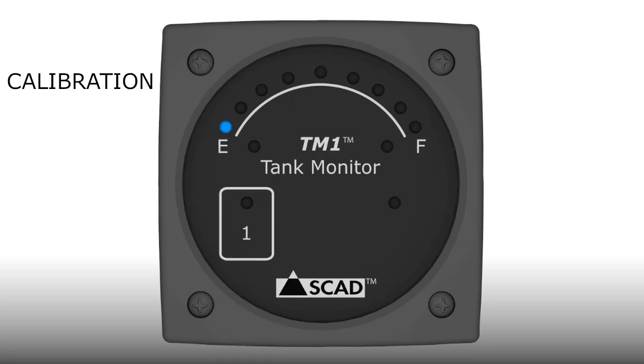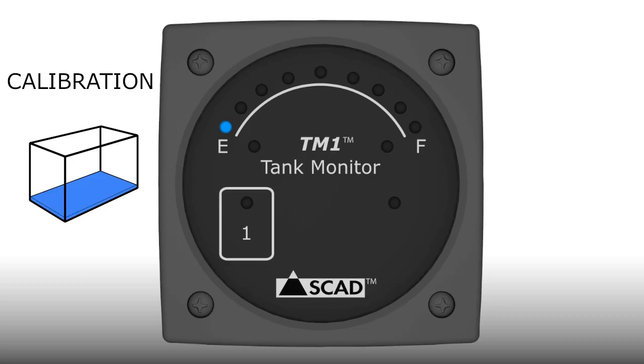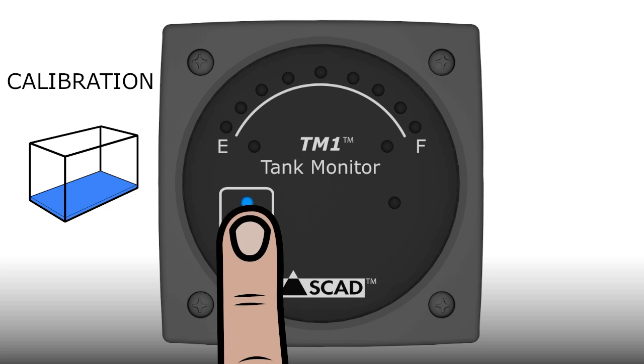You have to calibrate the monitor when the tank is actually empty or full. Both conditions must be set. Since it's not practical to calibrate both at once, you can calibrate the second condition later by entering the software setup and waiting for the parameter options to cycle through, then touch the pad when the 3 center lights are flashing. When the E light is flashing, you can set the empty calibration by touching the pad.